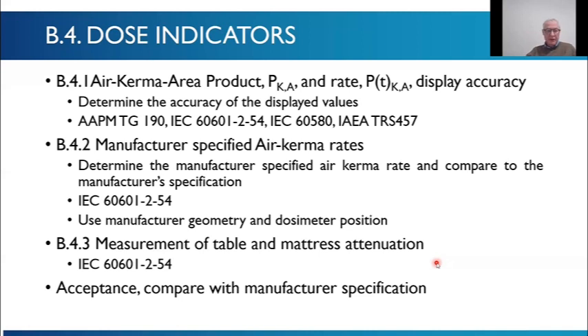I'm not going to say very much about dose indicators because I'd like to get on to the image quality. But obviously we test things like the air kerma area product display accuracy. So you make an explicit measurement of the air kerma and the field of view and calculate yours, and compare it to the one that's displayed. Then the manufacturer air kerma rates: measure it using manufacturer geometry and dosimeter position and compare what's on the screen to what you have. Measurement of the table and mattress attenuation. Again, these are IEC specified manufacturer specifications that you will compare against your measurements, okay?